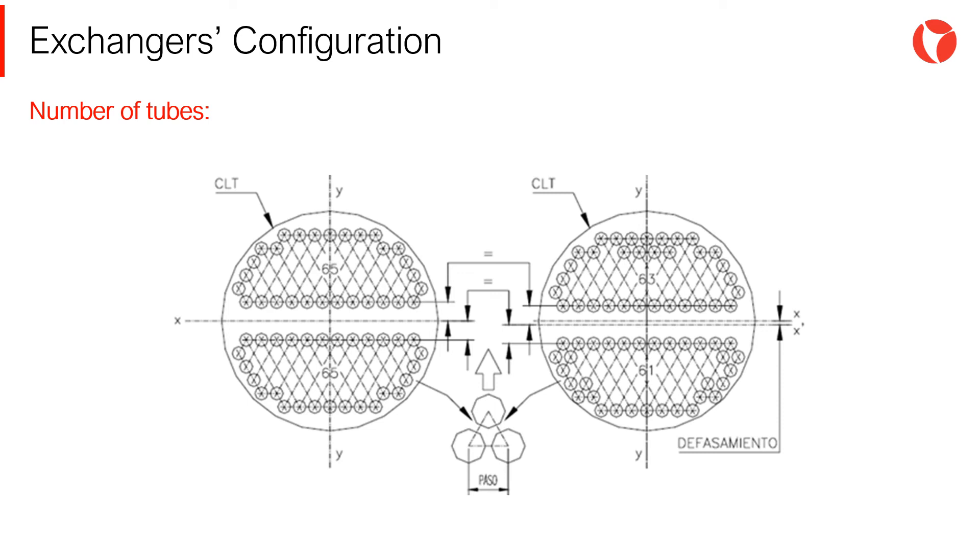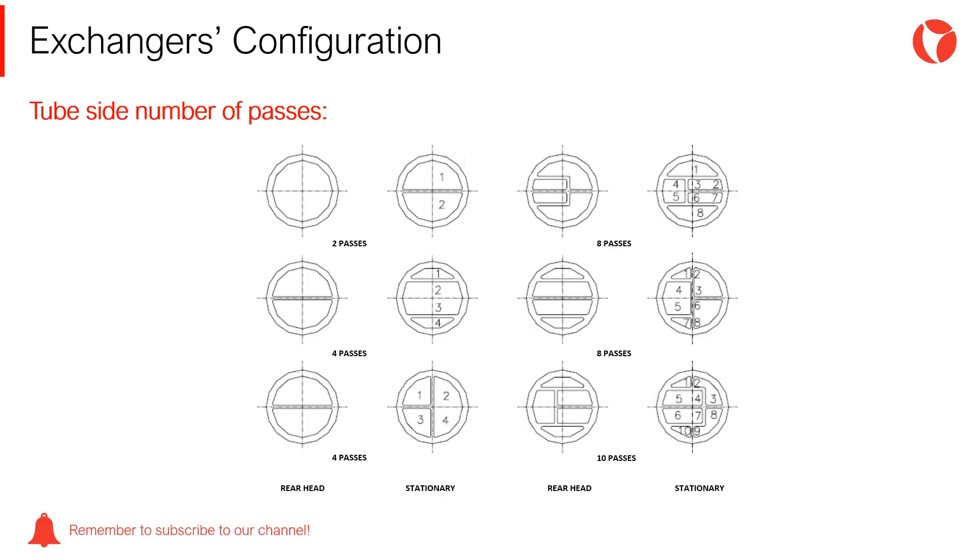When the number of passes is bigger than one, the same amount of tubes shall be arranged on each pass partition. This condition is not always met. At most, a 3% maximum difference in the number of tubes between passes may be accepted. The arrangement of partition plates in stationary rear or floating heads determine the number of times the tube side fluid changes direction. This is the number of passes of a shell and tube heat exchanger.